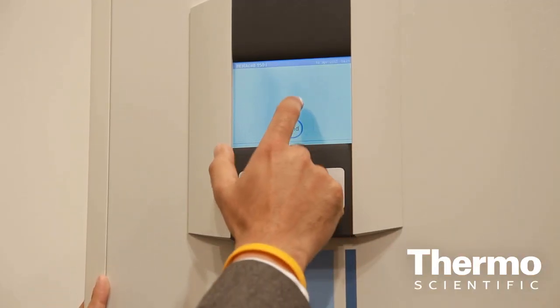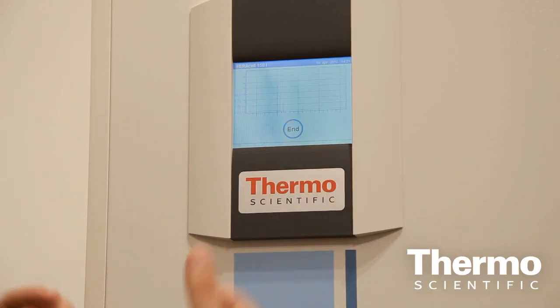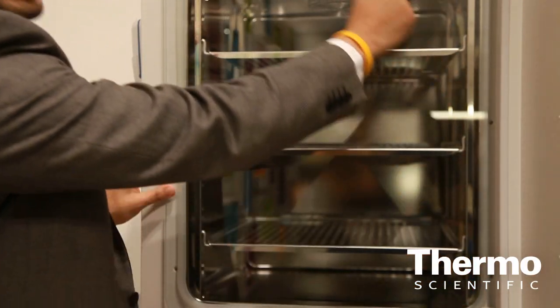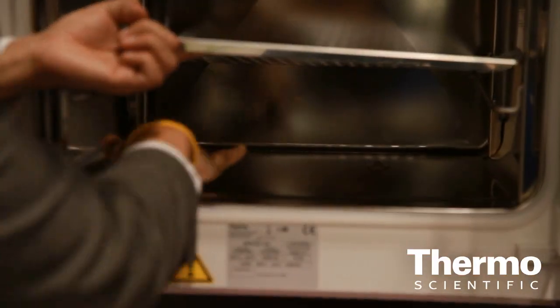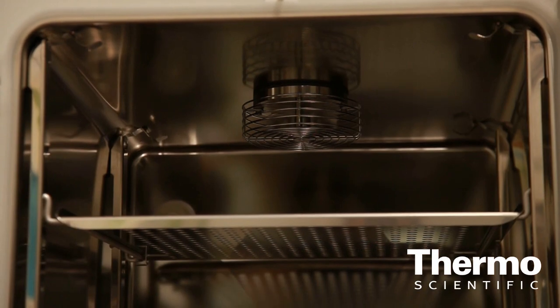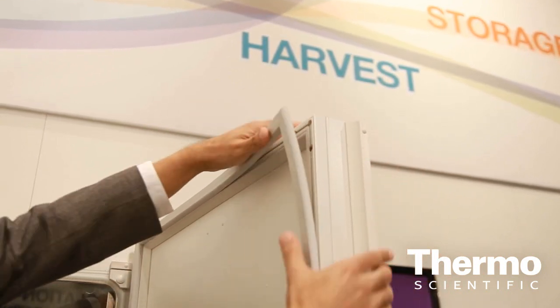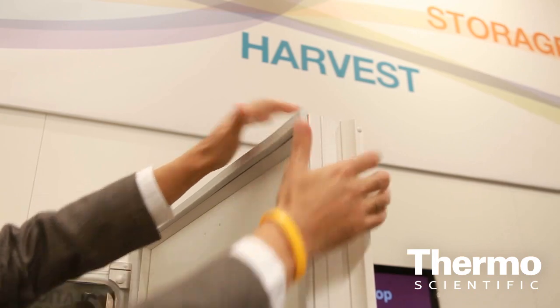And how exactly are we doing this with innovation? With IonGuard being just the next in a series of innovations that we've introduced, it's a silver antimicrobial matrix which covers all the internal surfaces. And what that means is you eliminate 99.9% of the most common microorganisms within 24 hours. The benefit to the user is that where they would have to think about cleaning the incubator after contamination has occurred, they have that peace of mind where they can prevent the contamination occurring in the first place.